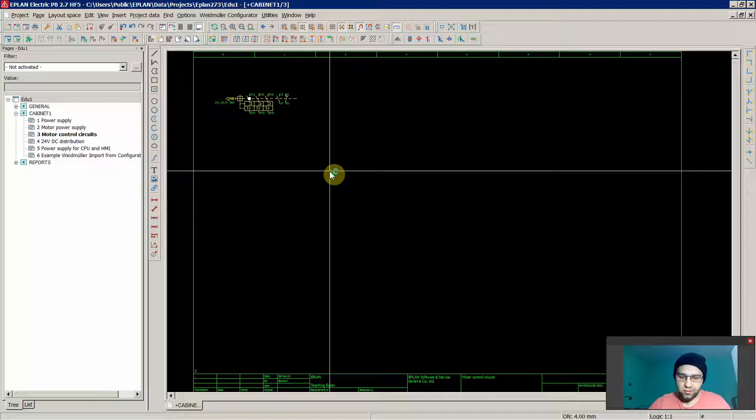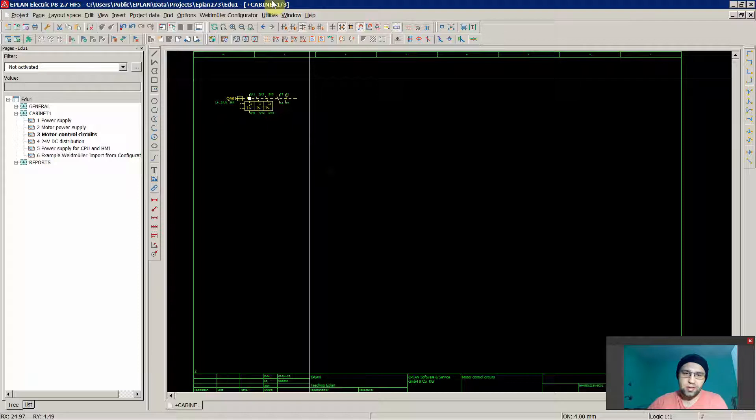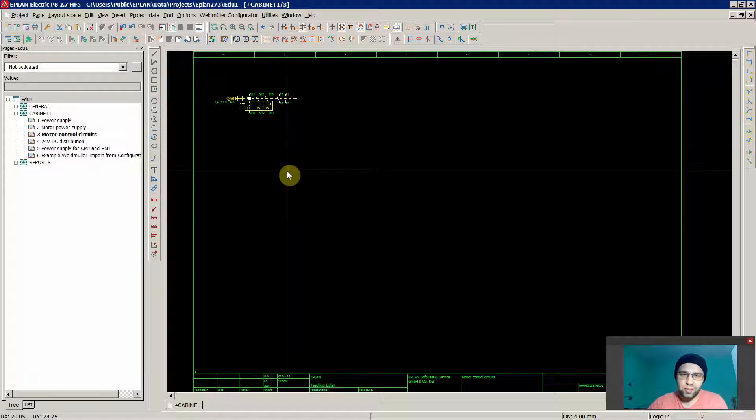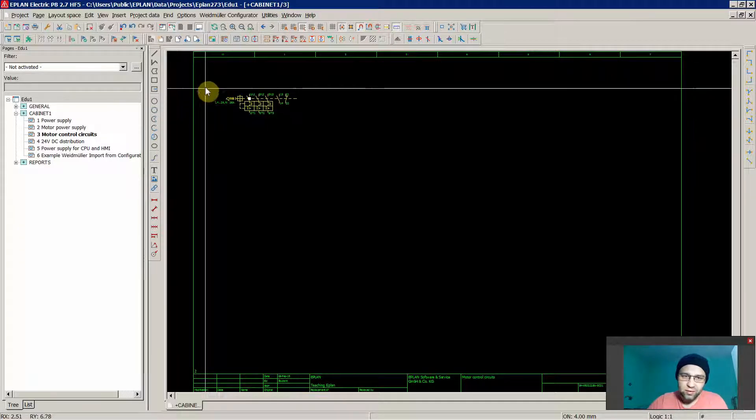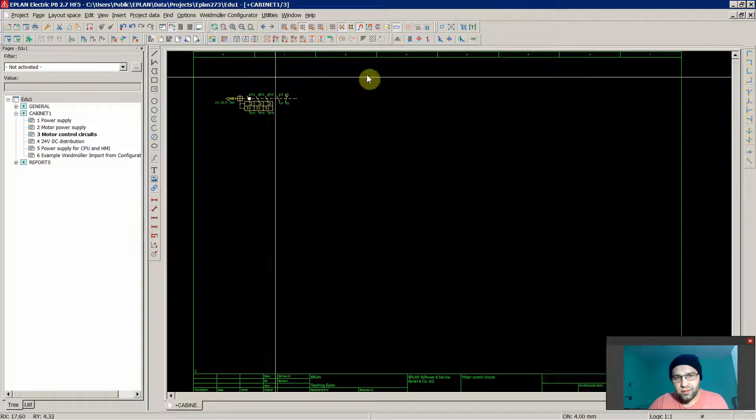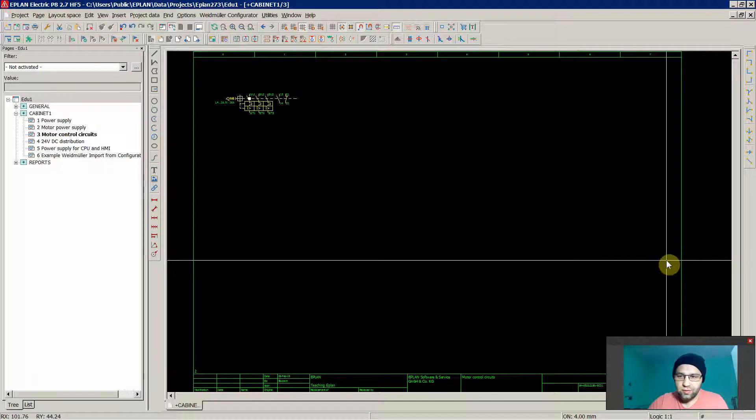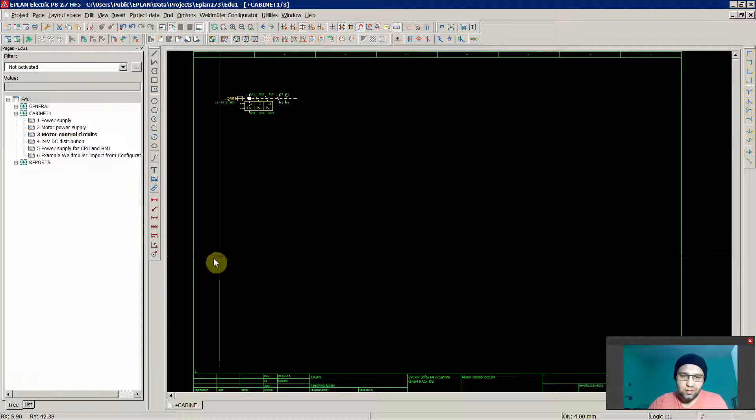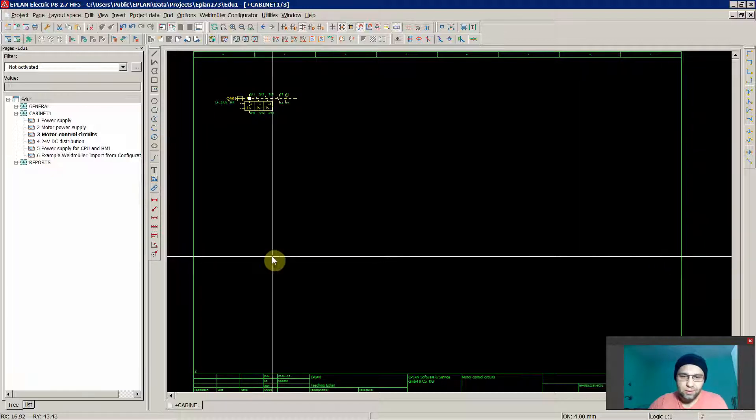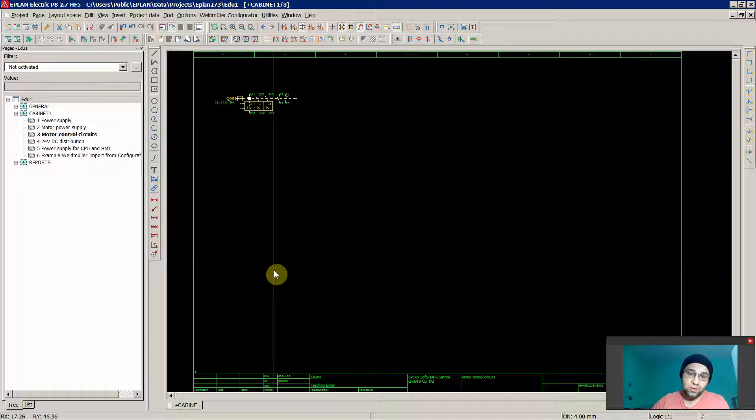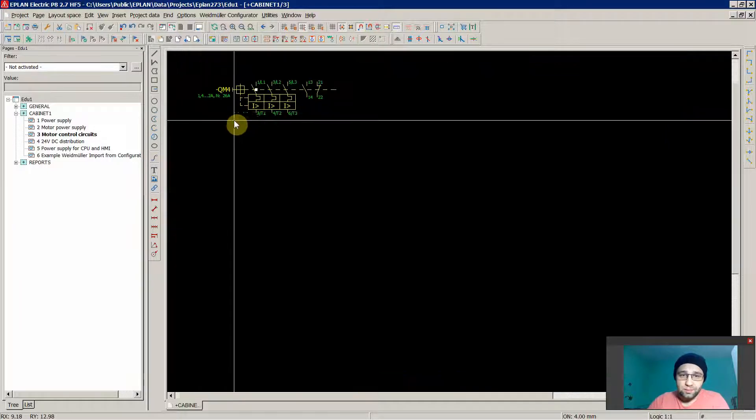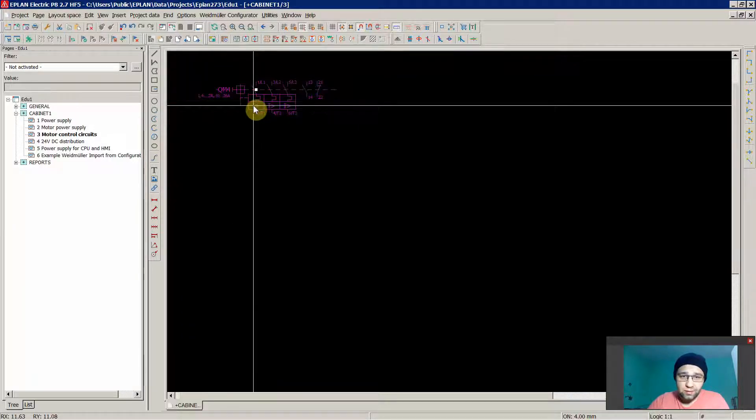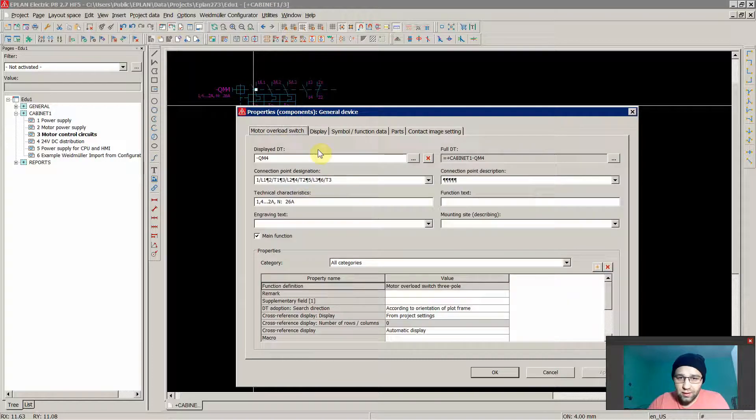The next one would be very useful. If you press letter U on your keyboard when you have some hidden objects, for example you edited your plot frames and you want to have some reference lines for your phases or at the bottom, or PE line for ground conductor and neutral conductor, in case you would like to see them but you wouldn't want to plot them. Let me show you how this works. We will edit this element a little bit, we'll say that the display, just the DT device tag of the element would be visible, so click yes invisible.